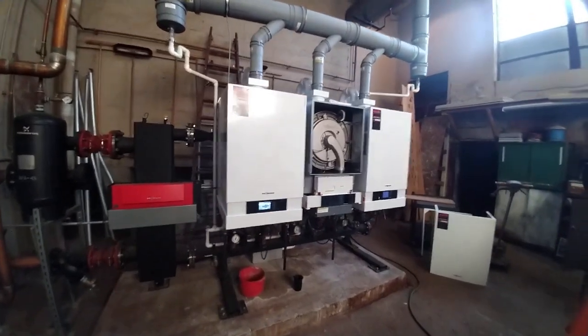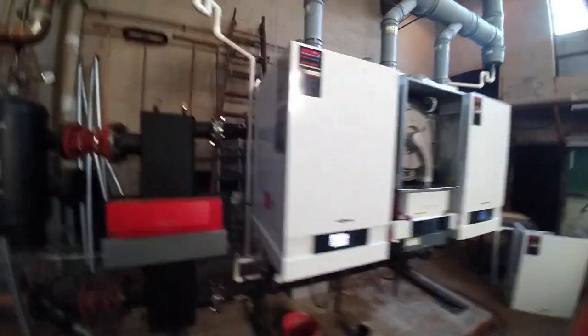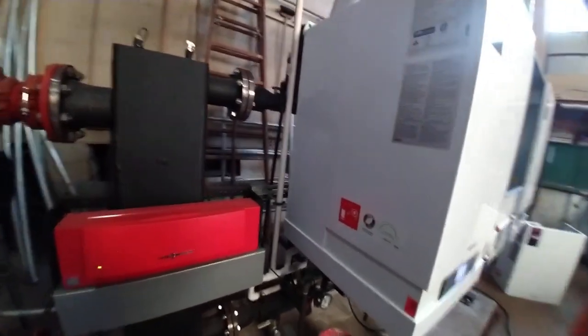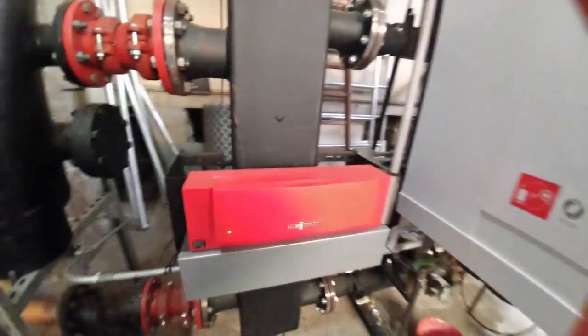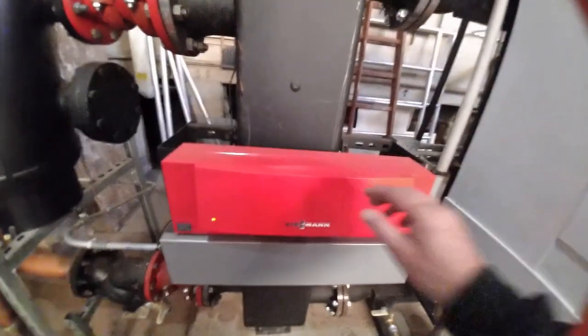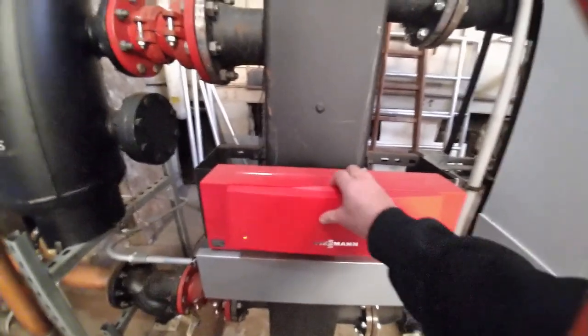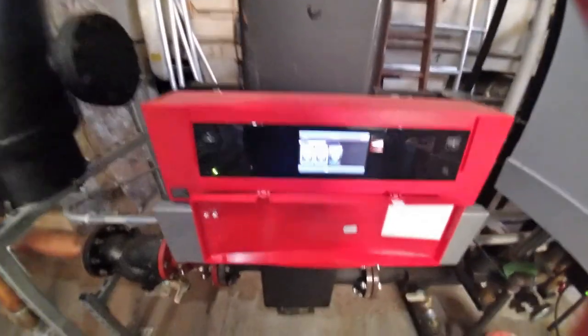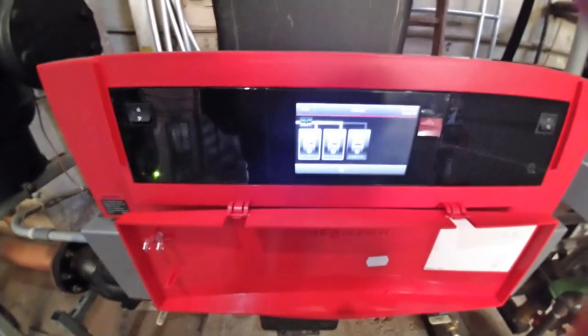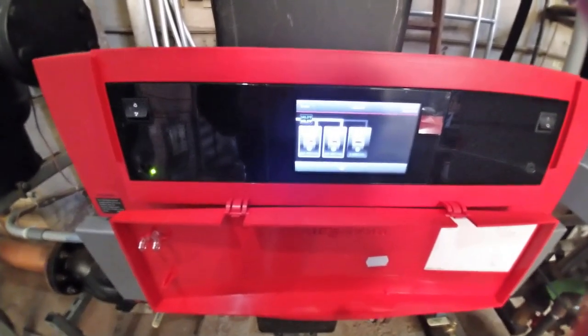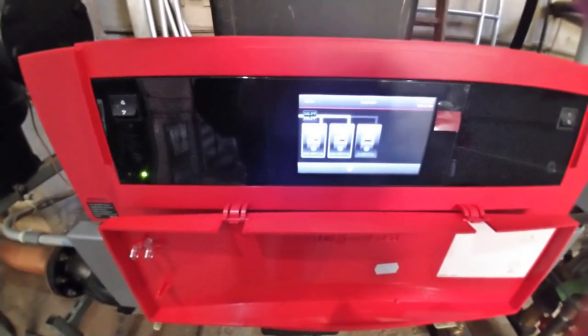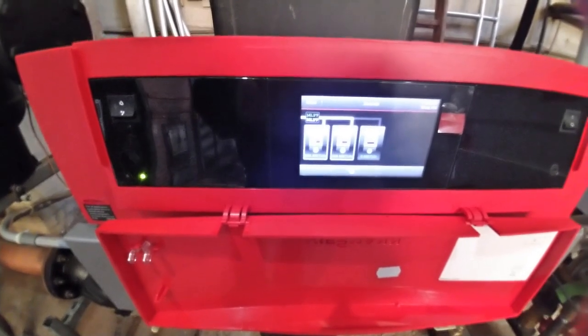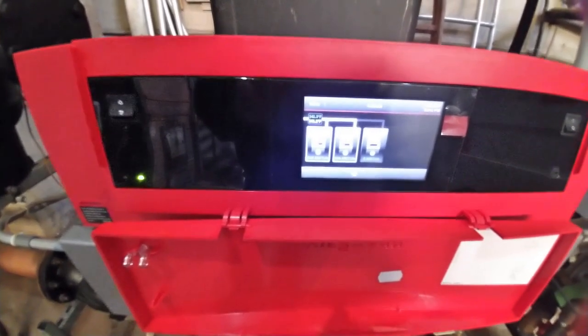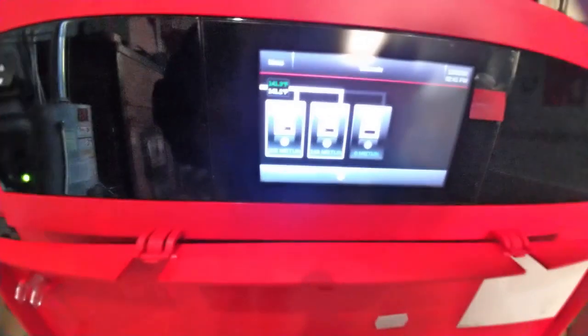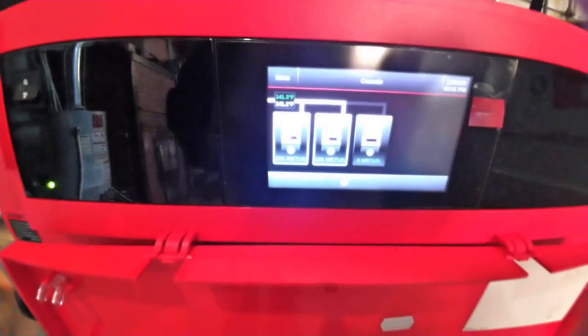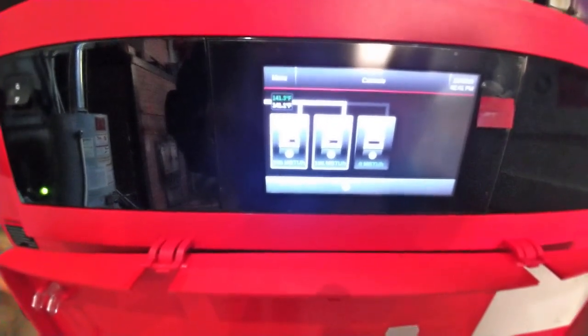You can put these on a rack system, which these are, and connect them all together. We're using a staging module which ties all the boilers together. This actually shows you a lot of the settings, but briefly it's showing right now 2 boilers running and giving us the modulated input of one at 205,000 BTUs an hour, second one at 206,000 BTUs an hour, and another one at 0.